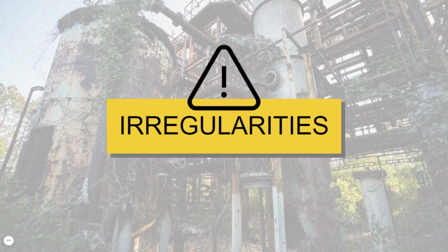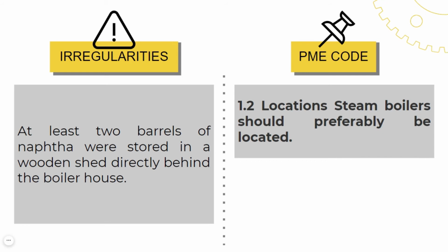The impact of the disaster could have been minimized if they had fixed some irregularities present in the factory at the time. One of the safety standards that were neglected is that at least 2 barrels of naphtha were stored in a wooden shed directly behind the boiler house. This violates the PME code, Chapter 7, on pressure vessels and boilers, section 1.2, where it is stated that steam boilers should preferably be located in detached buildings of fire-resistant construction used for other purposes and situated not less than 3 meters from buildings not forming part of the factory, or in structures of fire-resisting materials, preferably stone or concrete walls, connected to or in close proximity to the other factory buildings.